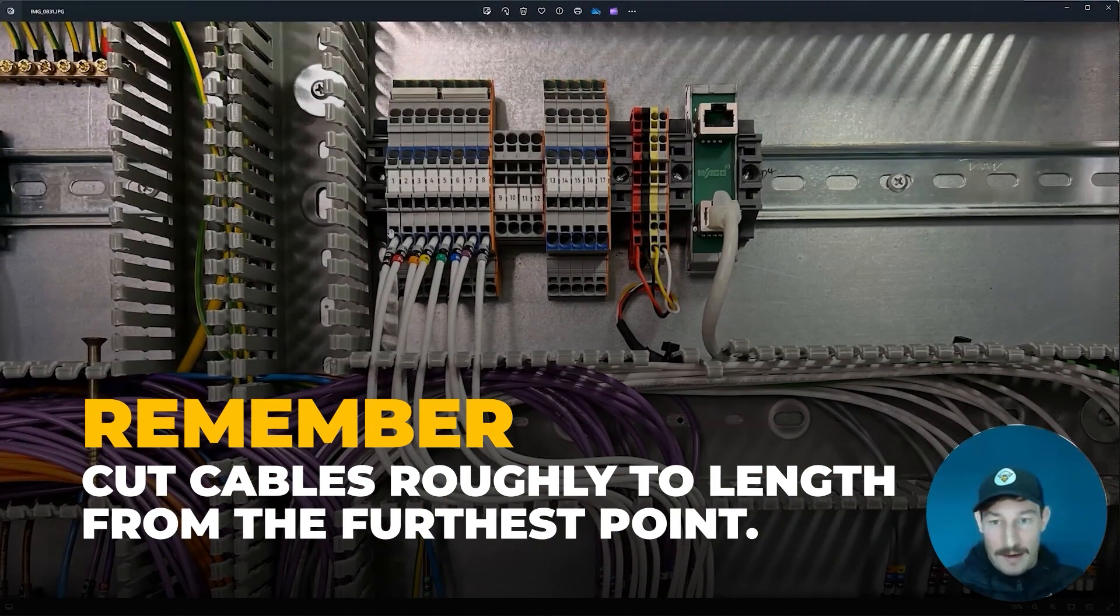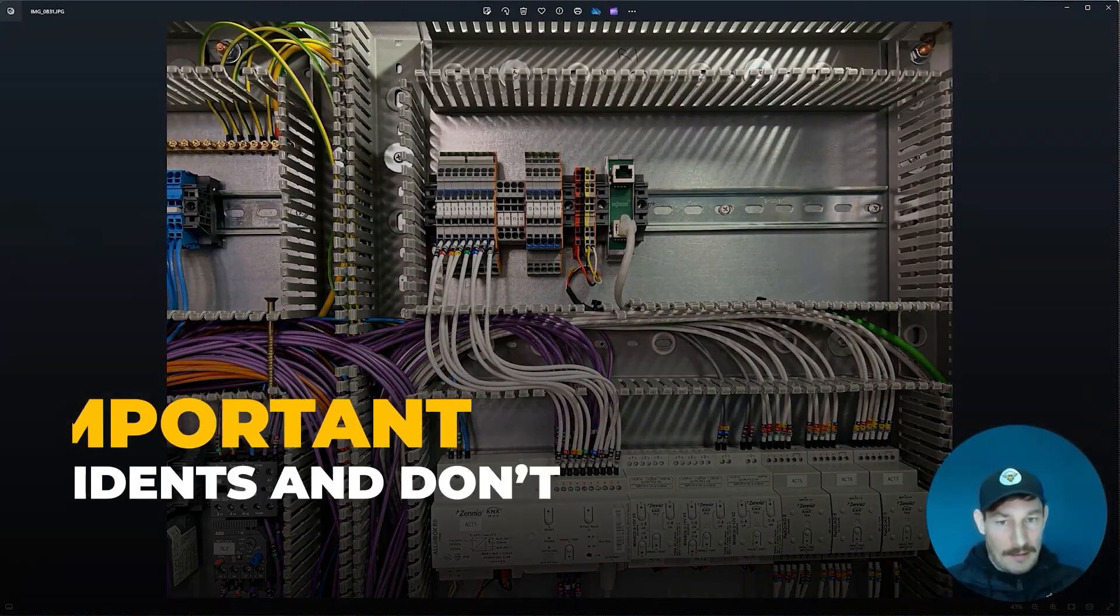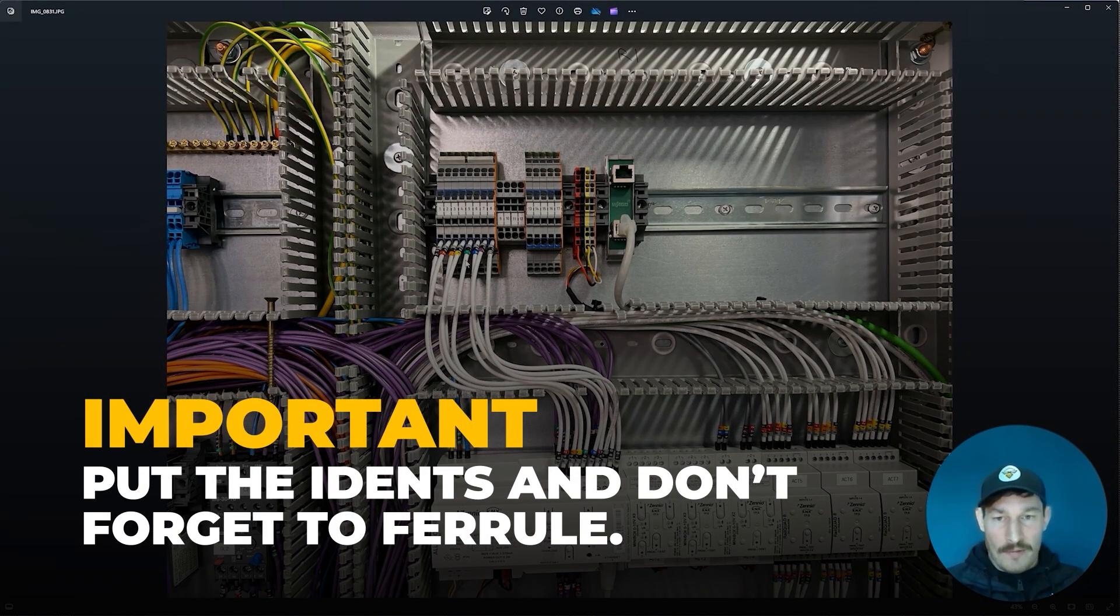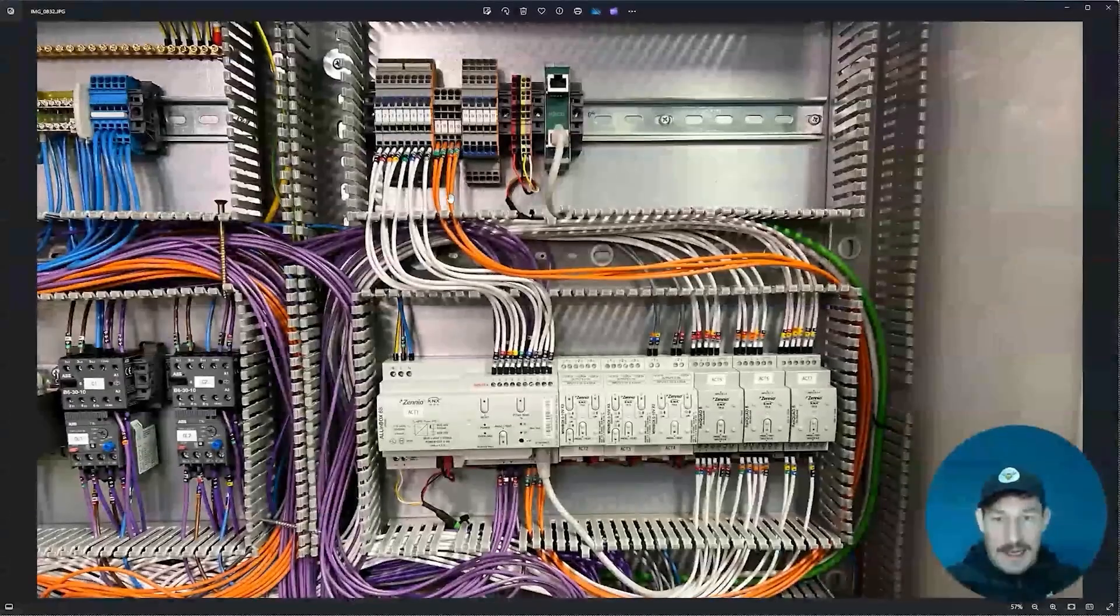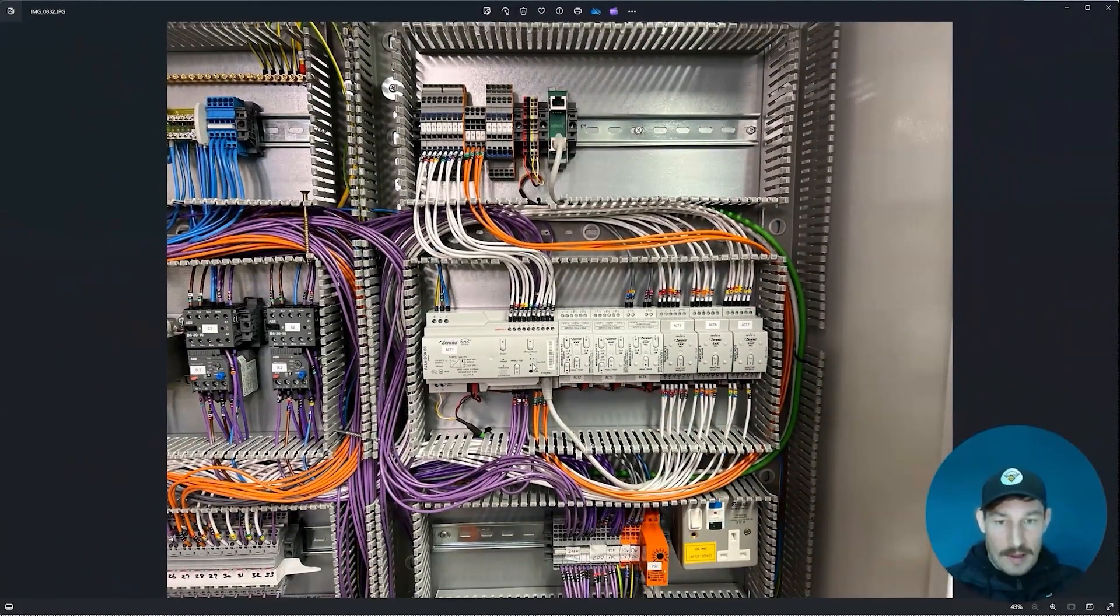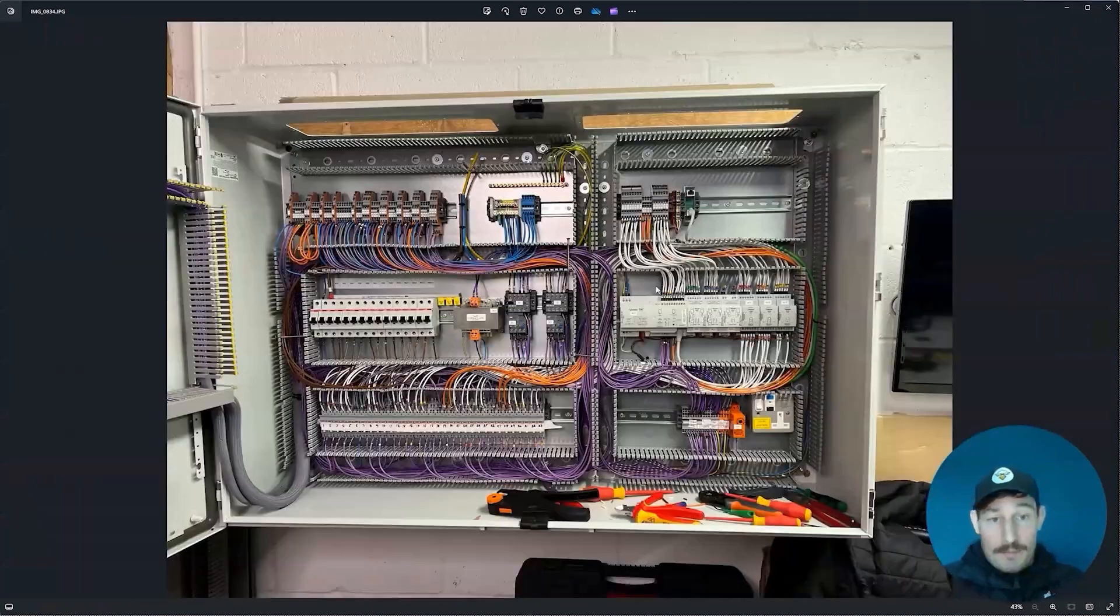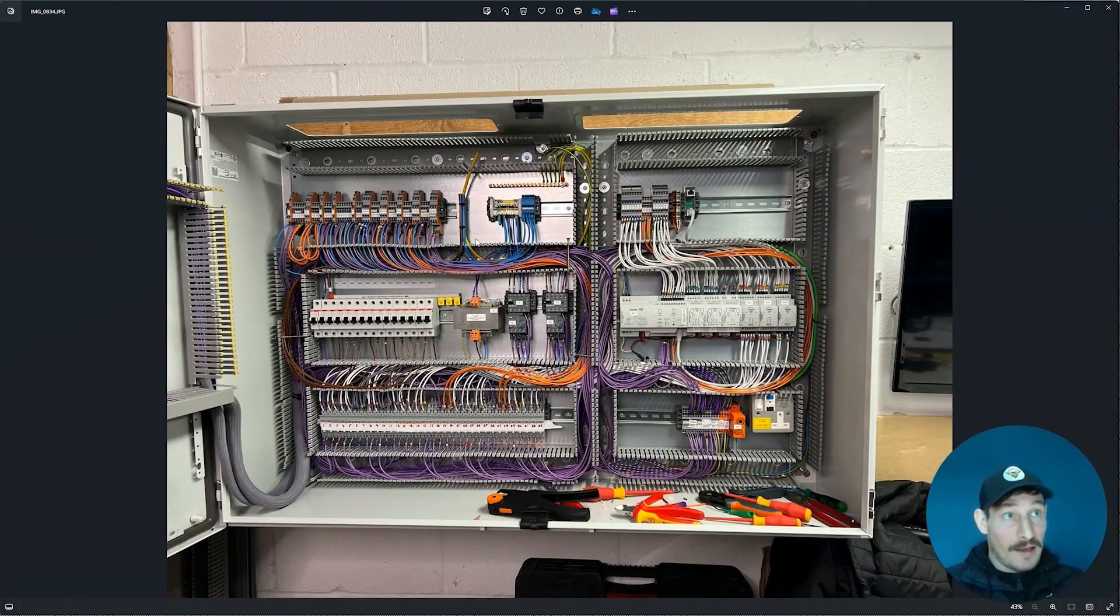I'll just cut all these cables roughly to length. I usually go from the furthest point here to the furthest point over here and then cut all those cables the same length, put the idents on them and ferrule them, and away we go. You can see the circuits—they're going off here to relays, relay control. That's basically it guys for the terminal blocks.